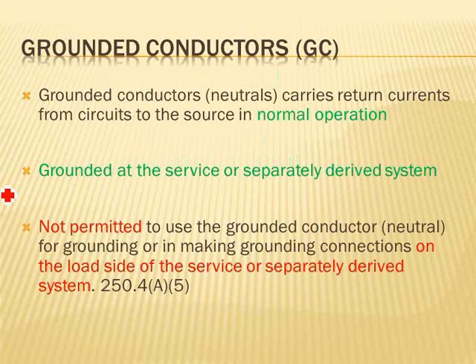With a few exceptions, remember that range in the old days and the range replacement, they allowed you to do what? To use the grounded conductor, the neutral, as an equipment grounding conductor in an existing range. Dryers, that was an exception. On the farm, feeders, if you're going to a separate building, they allow you to use the grounded conductor. So if you have a 3-phase system, you run 4 wires, 3 phases and neutral, to the second building, knowing that your grounded conductor can be used as an equipment grounding conductor.